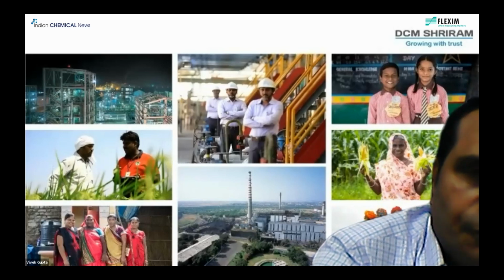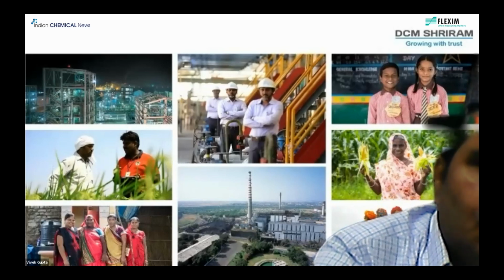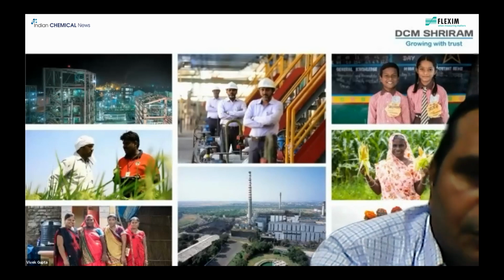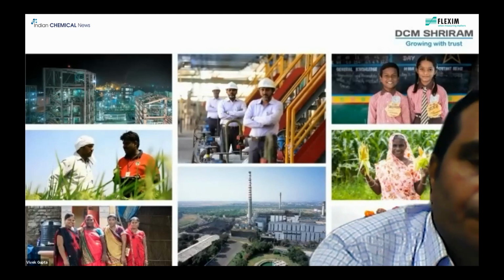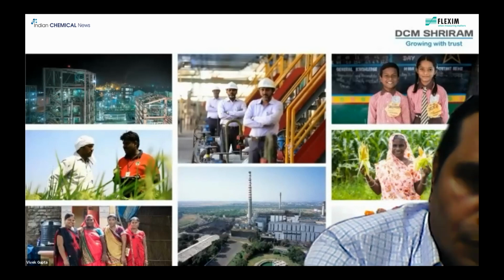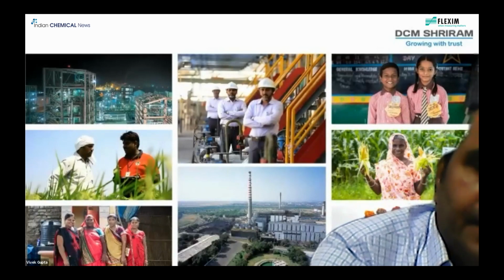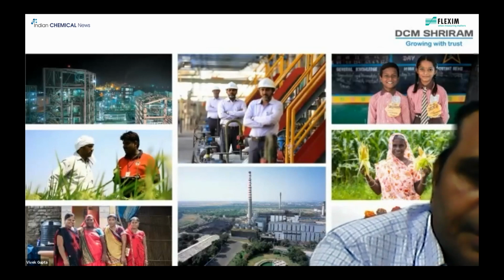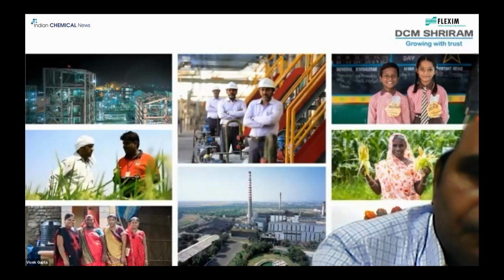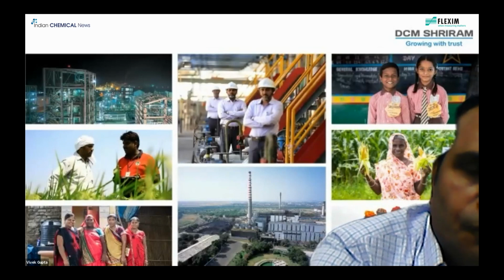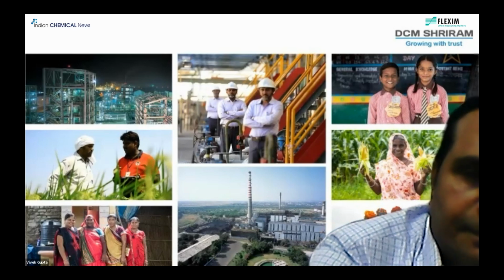So these are the things which we are following, but certainly as of now, other than cooling water, we are not measuring the steam flow through clamp on. It is only with the use of either the flow nozzles or the orifice plate with the DP transmitter. But certainly with this knowledge sharing session, I think we will plan in future for some of the corrosive fluids to put a clamp on for the better optimization of the plant. Thank you. Thank you, Vivekji.